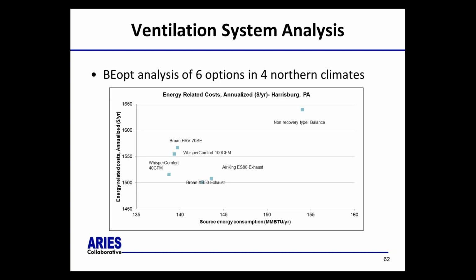We really would like to have heat recovery ventilation instead of just an exhaust fan. We looked at 6 options using BEopt, Building Energy Optimization software, in a variety of northern climates where we'd expect that to be more attractive in terms of a total energy-related cost per year metric. This plot shows those 6 items: 3 different HRVs, 2 exhaust fans, and then just a balanced ventilation without heat recovery.